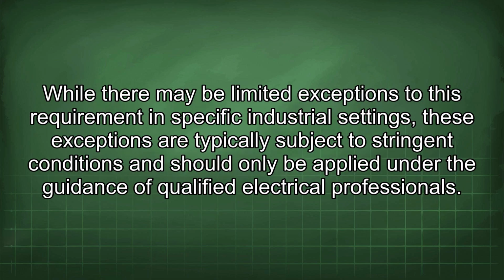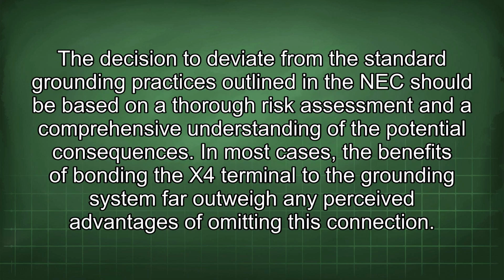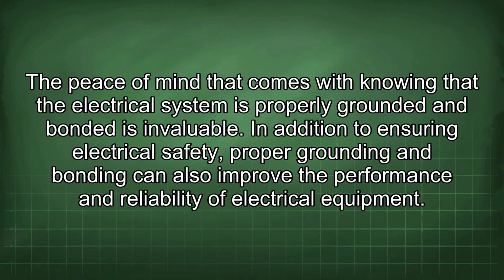While there may be limited exceptions to this requirement in specific industrial settings, these exceptions are typically subject to stringent conditions and should only be applied under the guidance of qualified electrical professionals. The decision to deviate from the standard grounding practices outlined in the NEC should be based on a thorough risk assessment and a comprehensive understanding of the potential consequences. In most cases, the benefits of bonding the X4 terminal to the grounding system far outweigh any perceived advantages of omitting this connection. The peace of mind that comes with knowing that the electrical system is properly grounded and bonded is invaluable.